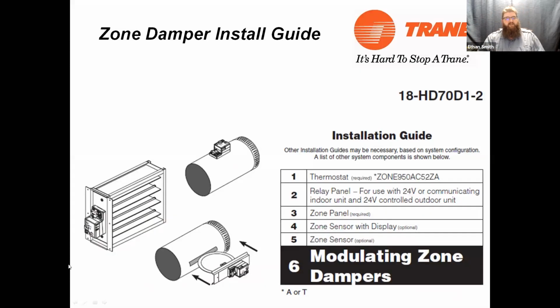There's kind of a picture of all the Trane zoning dampers. They come in various styles. We've got the rectangular frame dampers. You can get those in side or bottom mount motors. We have the round build-up dampers. They're already built into the housing. You just attach your ductwork to them. And then these are actually my personal favorite, which are the round retrofit dampers. So this is what I'm using on my system. Because all my ductwork's already installed, I can get an appropriately sized damper, cut a slot in it, and then this is fully gasketed, so you don't have any air leakage or anything like that. You just slide it in, center up your damper, and you're good to go.